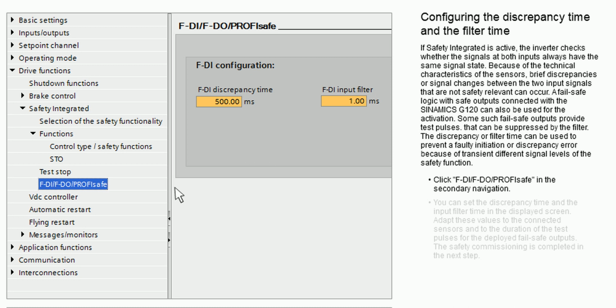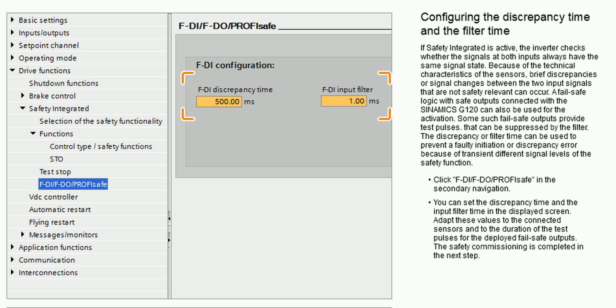Click FDI, FDO, PROFIsafe in the secondary navigation. You can set the discrepancy time and the input filter time in the displayed screen. Adapt these values to the connected sensors and to the duration of the test pulses for the deployed fail-safe outputs. The safety commissioning is completed in the next step.